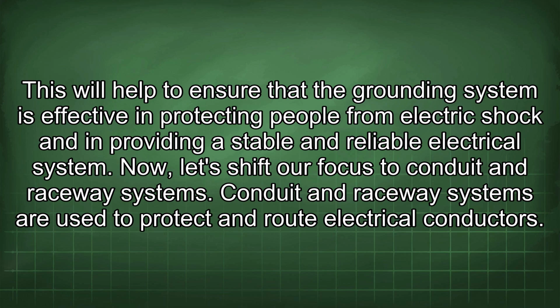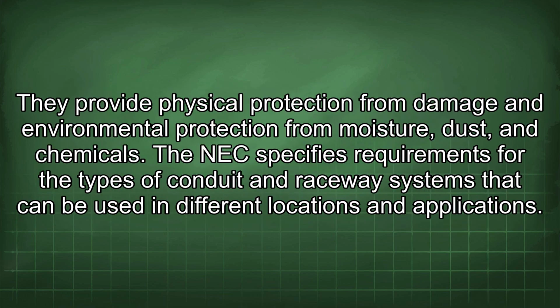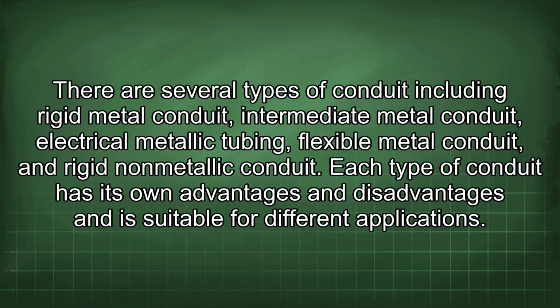Now let's shift our focus to conduit and raceway systems. Conduit and raceway systems are used to protect and route electrical conductors. They provide physical protection from damage and environmental protection from moisture, dust, and chemicals. The NEC specifies requirements for the types of conduit and raceway systems that can be used in different locations and applications. There are several types of conduit, including rigid metal conduit, intermediate metal conduit, electrical metallic tubing, flexible metal conduit, and rigid non-metallic conduit.